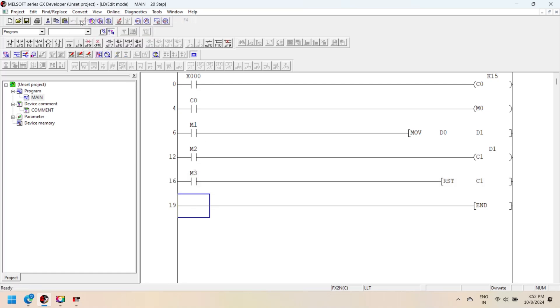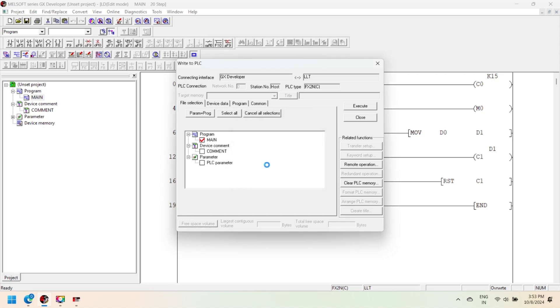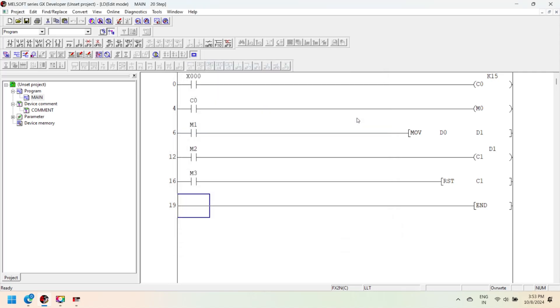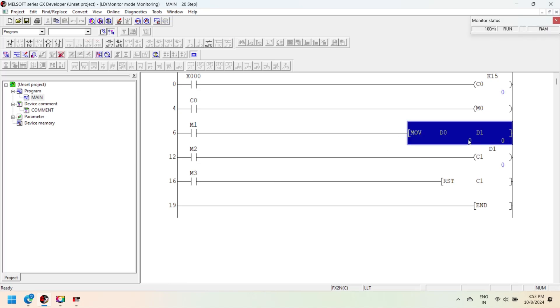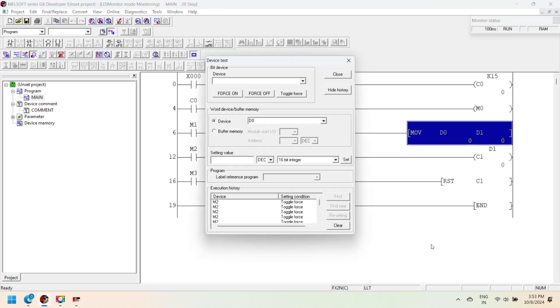Now convert the program and write it to the controller. As we know, the MOVE instruction moves the source value to the destination. Here D0 is the source register and D1 is the destination register; D1 is also the preset value of counter C1. When the value is set to D0 and the input bit is activated, the counter preset value is set. When the input bit changes from off to on, the counter increments by 1. If the counter current value equals the preset value, the counter done bit is set.